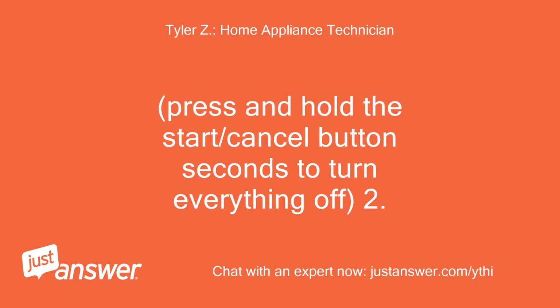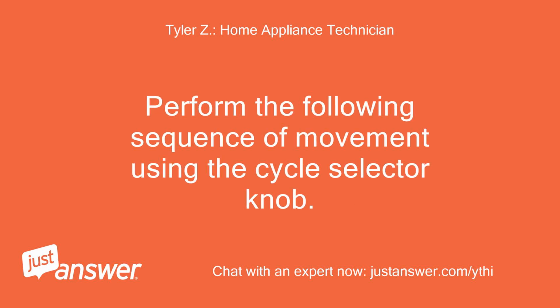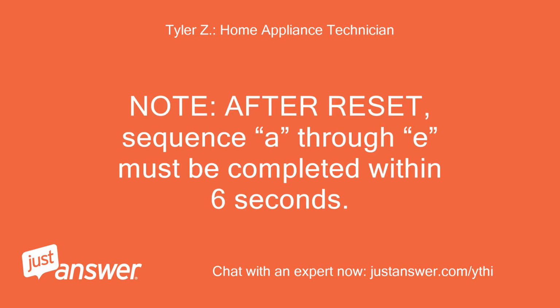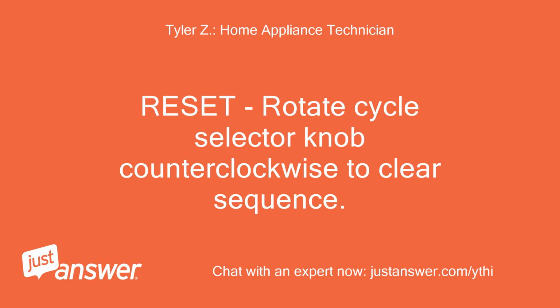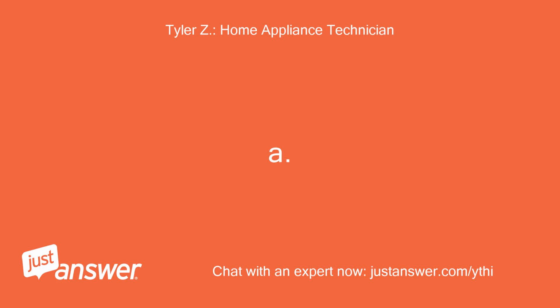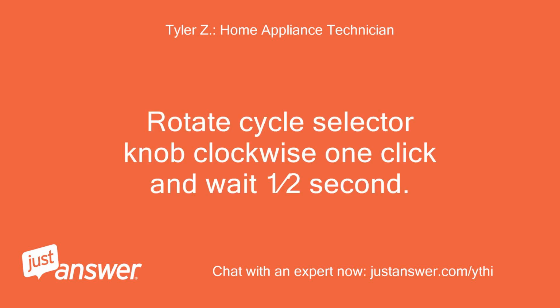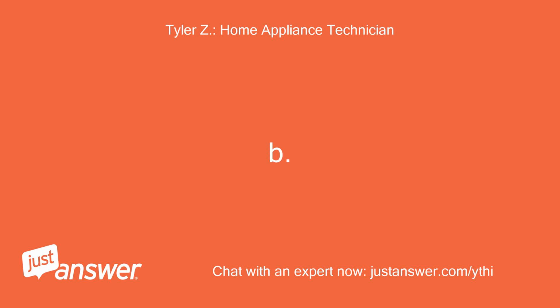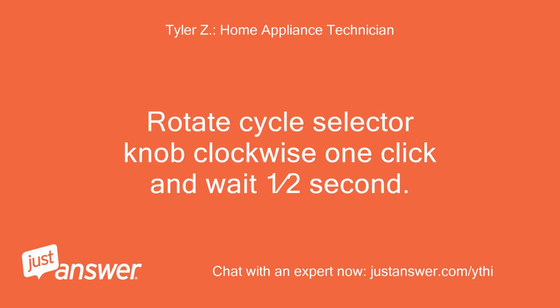2. Perform the following sequence of movement using the cycle selector knob. Note, after reset, sequence A through E must be completed within 6 seconds. Reset, rotate cycle selector knob counterclockwise to clear sequence. A. Rotate cycle selector knob clockwise 1 click and wait half a second. B. Rotate cycle selector knob clockwise 1 click and wait half a second.